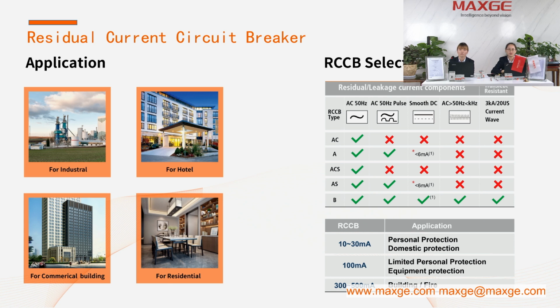Our newly launched B type RCCB is designed for industry applications where there is an increasing use of devices like electric vehicle chargers, frequency converters, medical equipment, and UPS systems. 10 to 30 mA is for personal and domestic protection, and 100 mA is for limited personal protection and equipment protection. 300 to 500 mA is for building or fire protection.